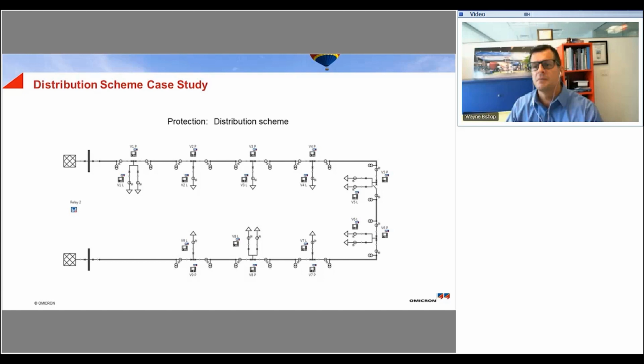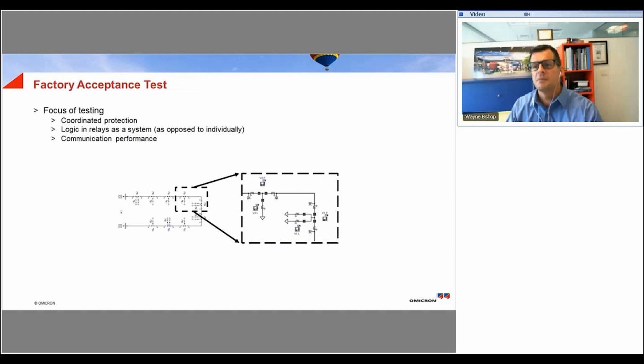As you can see from the scheme, it consisted of 9 separate locations, each with their own switchgear, and implemented within each were about 2 multifunctional relays, 1 on each primary switch and 1 on each load tap switch, and a variety of different communication equipment was also used. For the initial testing, typical testing is usually performed 1 relay at a time, where you verify each relay is working. You can test all of its protection elements, and this is very standard nowadays, right? It's usually done through element testing.